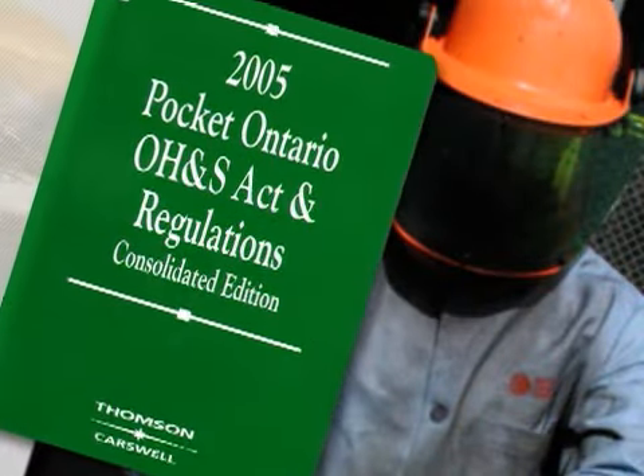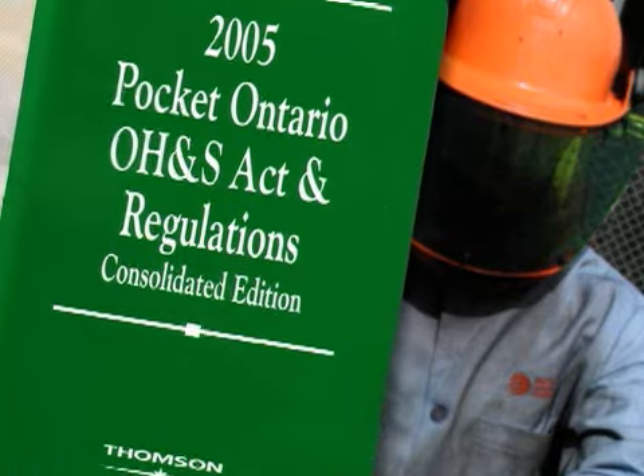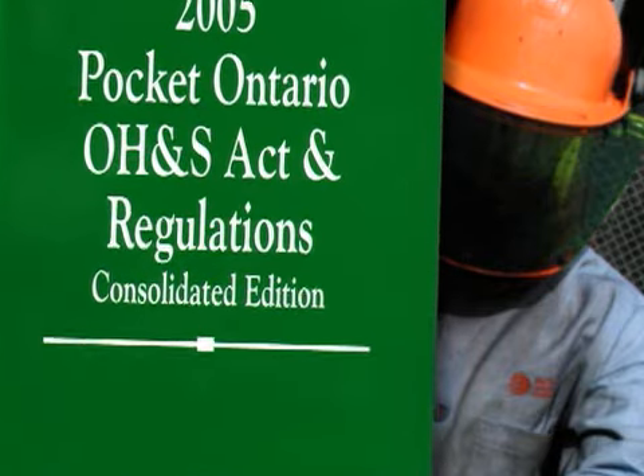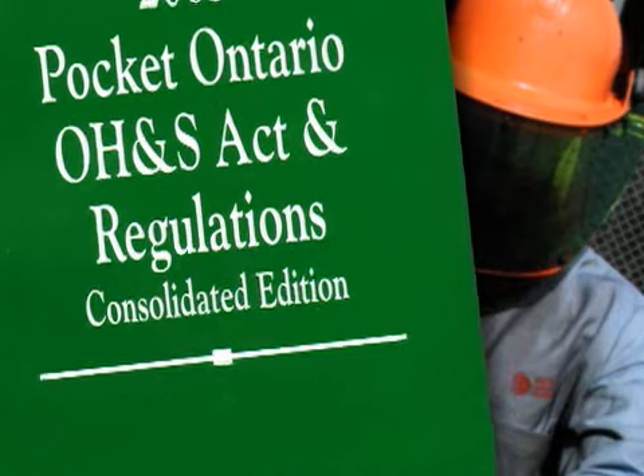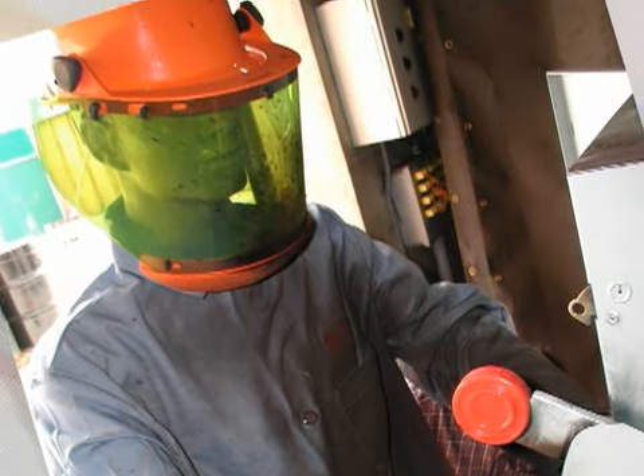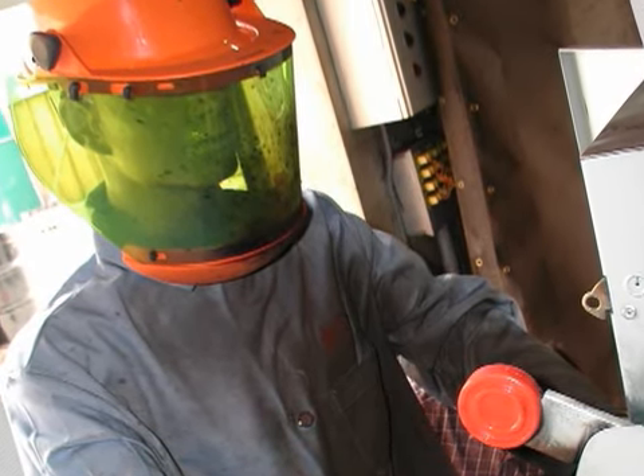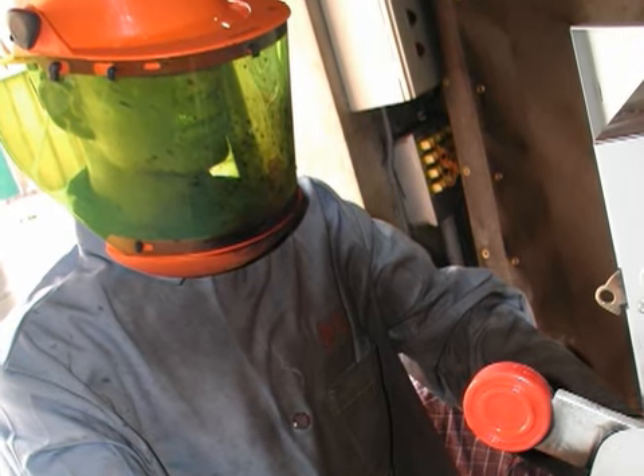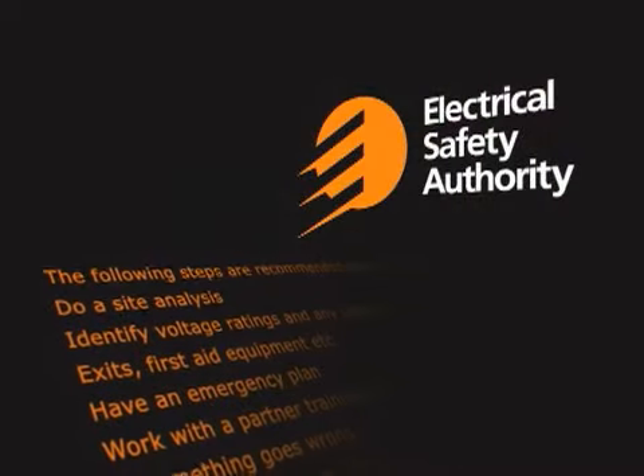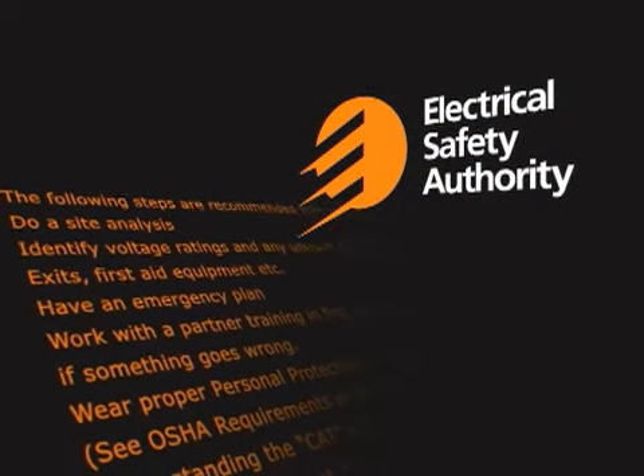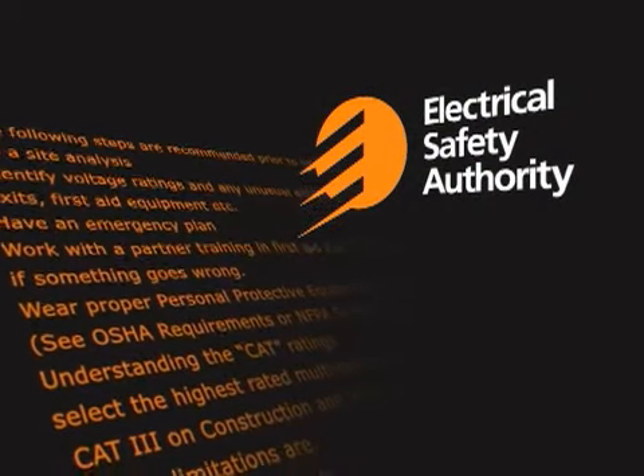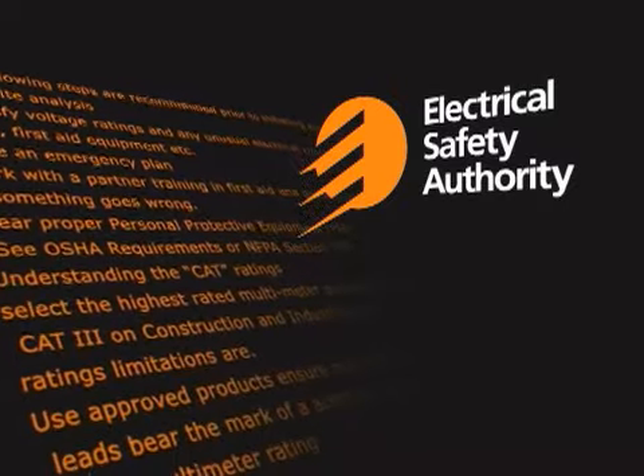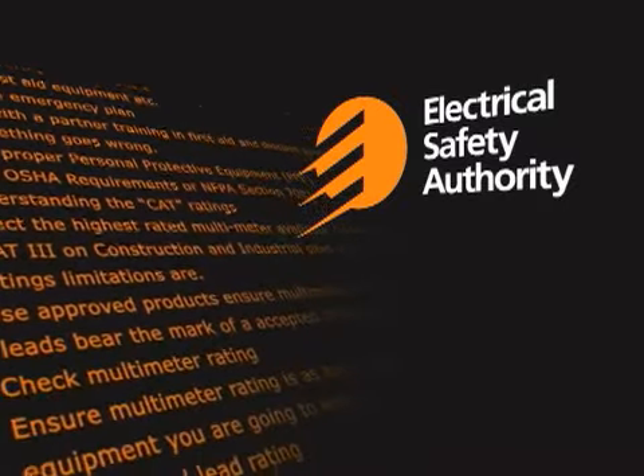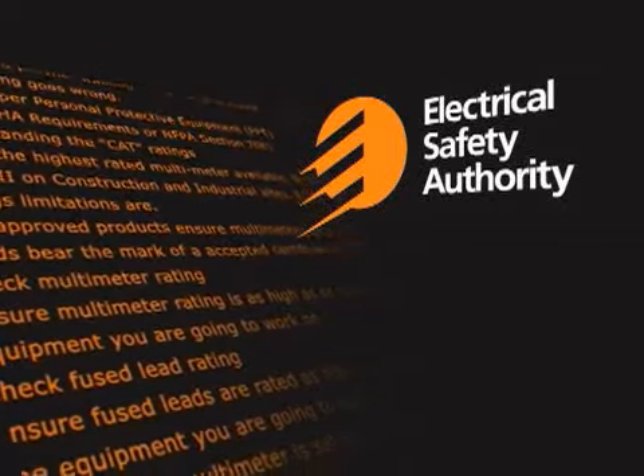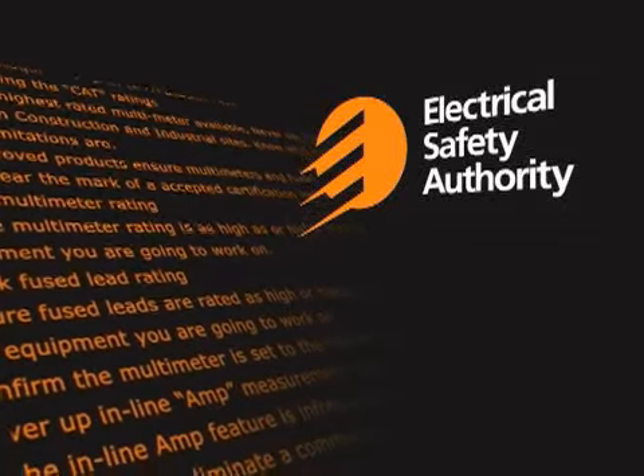The Occupational Health and Safety Act requires the use of personal protective equipment, or PPE, when testing live electrical systems. PPE provides an additional safety component, and as you can see, it can protect workers in the event of a meter failure. The Electrical Safety Authority recommends adopting safe work practices to reinforce a high level of safety performance. The Electrical Safety Authority's 15 basic safety steps are highlighted in the Safe Work Practice Guideline on this CD.